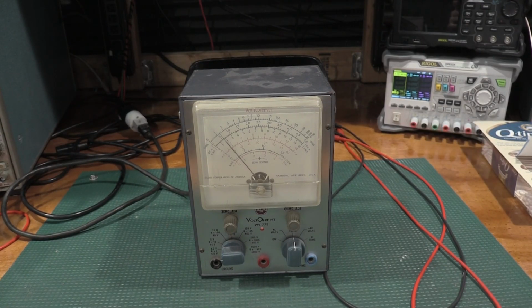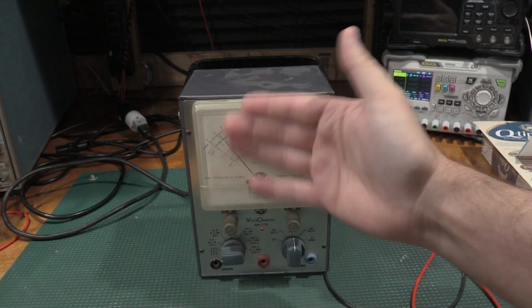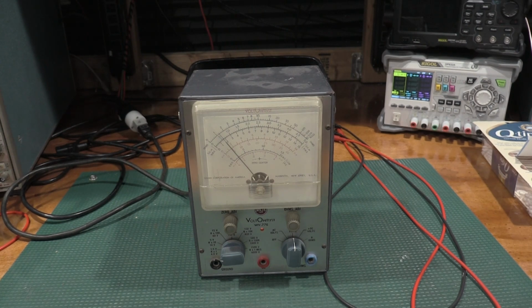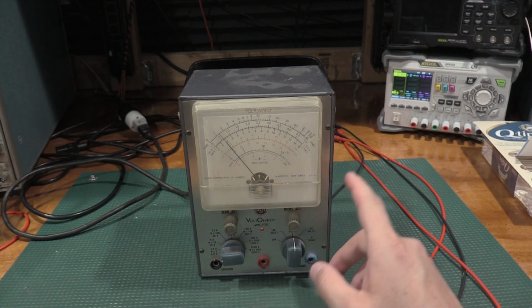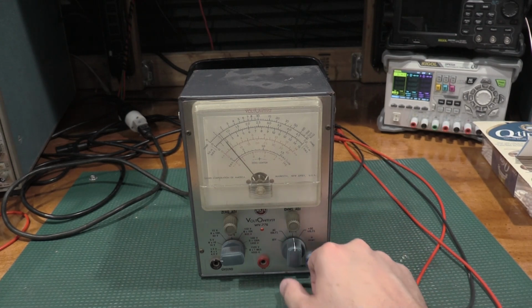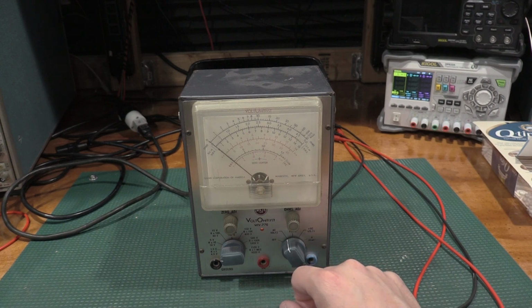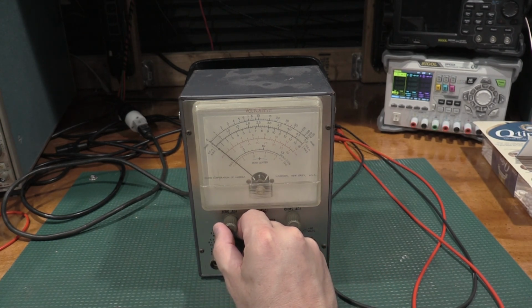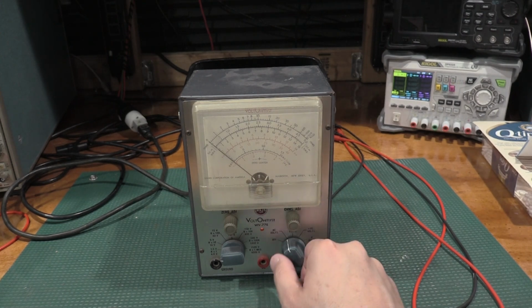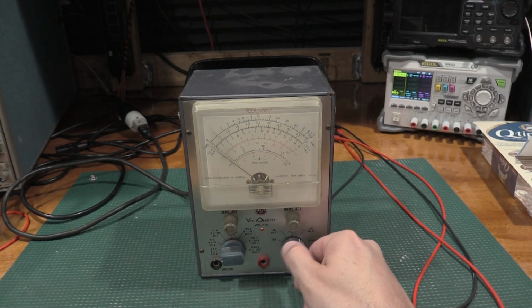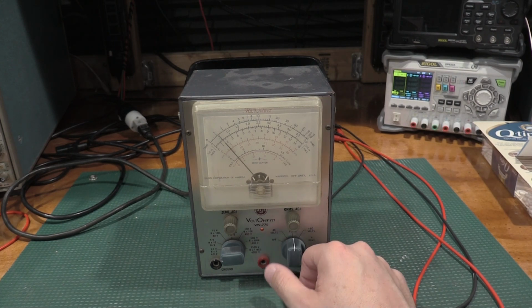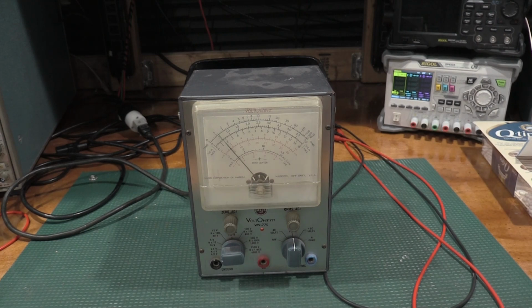Okay, well, I had to refresh the anti-static coating on the plastic meter because the meter face was moving around as I was moving my hand in front of it. It is not anymore, so we are good. However, I've got this set up to do the balance adjustment, and the balance adjustment is way off. So if I zero it on AC ohms, the mechanical zero is done. The meter zero needs to be done, but if I go to negative DC volts and positive DC volts, well, negative DC volts, we're way off. So we need to adjust this for zero movement when switching between the ranges.